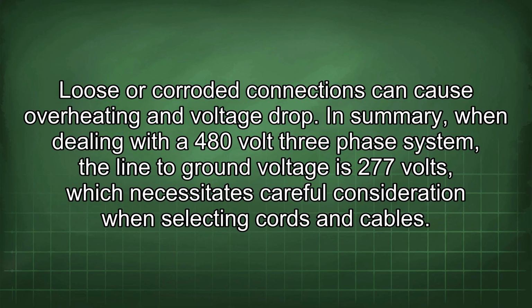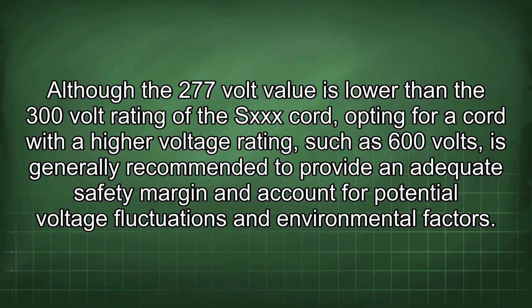In summary, when dealing with a 480-volt three-phase system, the line-to-ground voltage is 277 volts, which necessitates careful consideration when selecting cords and cables. Although the 277-volt value is lower than the 300-volt rating of the Sxxx cord, opting for a cord with a higher voltage rating, such as 600 volts, is generally recommended to provide an adequate safety margin and account for potential voltage fluctuations and environmental factors.